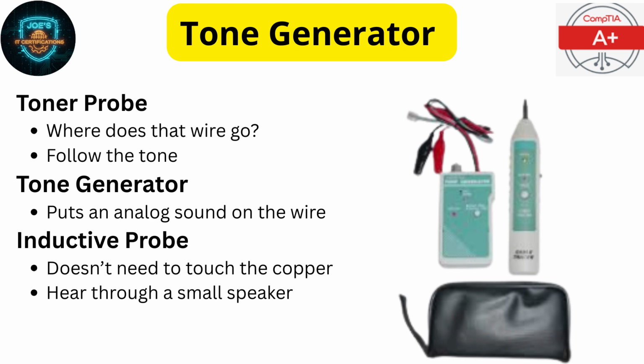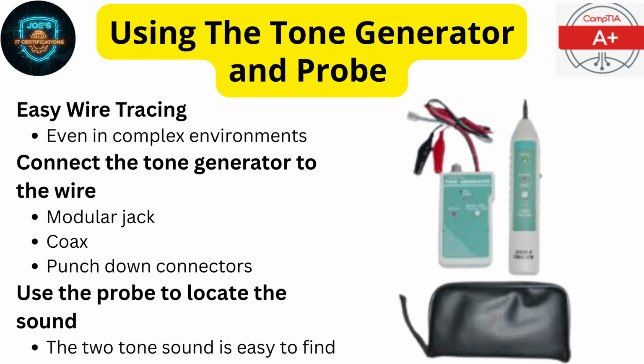This is really two different devices. One is the tone generator itself that you plug into the wire, and it puts an analog sound onto the wire. We obviously can't hear that sound with our own ears, so we need an inductive probe to find that sound without physically touching the copper inside the cable. This means if you have hundreds or thousands of cables in a closet, you can use these tools to easily find the end of any one of those wires.